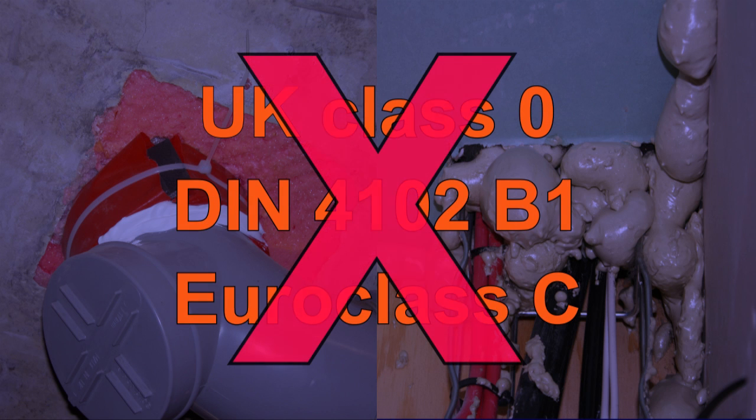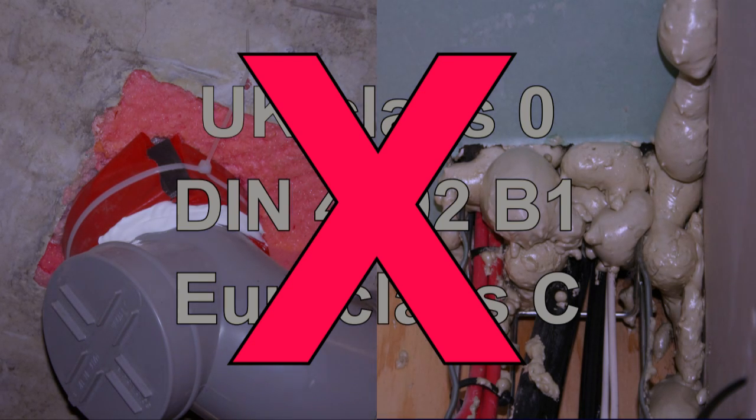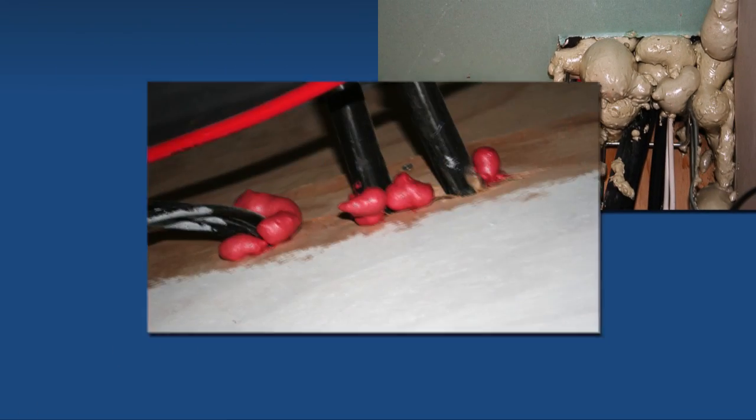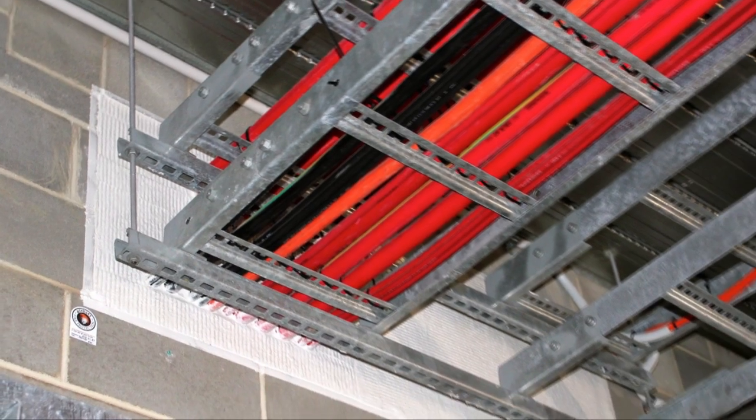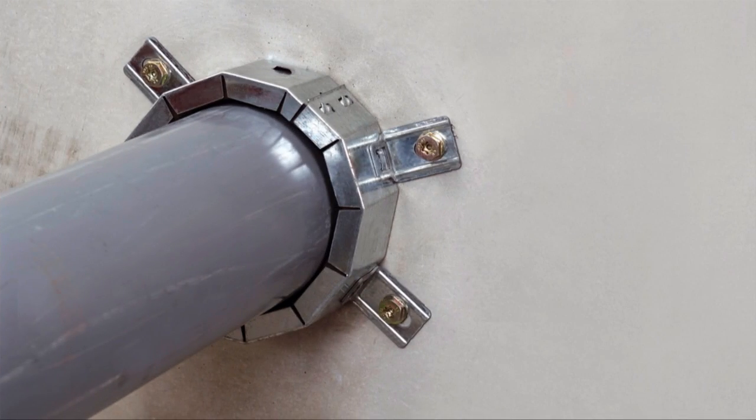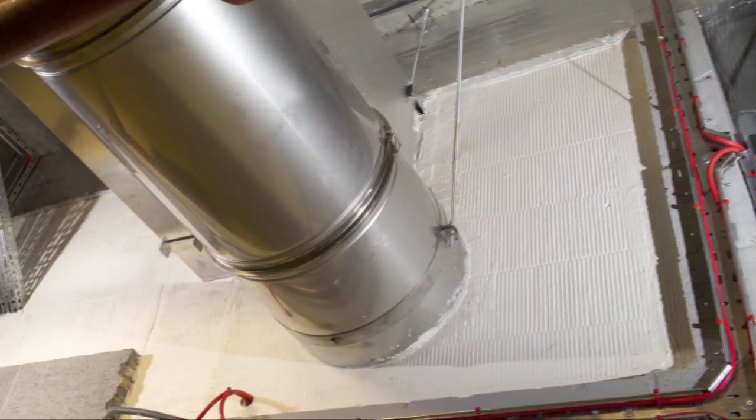These performances are no indicator of their ability to seal openings in compartment walls and floors with cables or pipes passing through them. Any installations fire-stopped with a PU foam whose performance has only been demonstrated using a reaction to fire test, or which only claim a reaction to fire class, should not be used for fire-stopping.